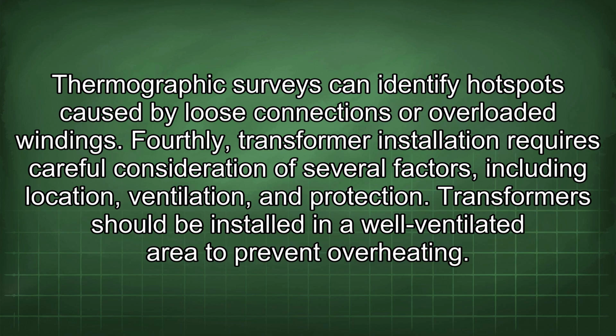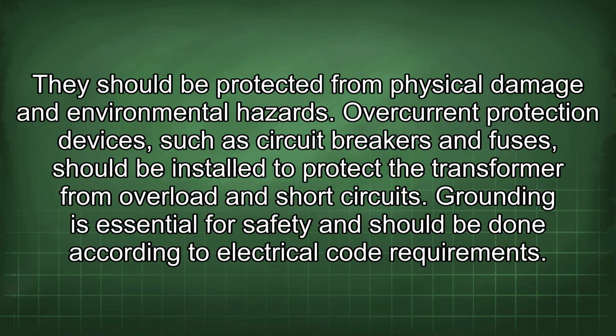Fourthly, transformer installation requires careful consideration of several factors, including location, ventilation, and protection. Transformers should be installed in a well-ventilated area to prevent overheating. They should be protected from physical damage and environmental hazards. Overcurrent protection devices, such as circuit breakers and fuses, should be installed to protect the transformer from overload and short circuits. Grounding is essential for safety and should be done according to electrical code requirements.